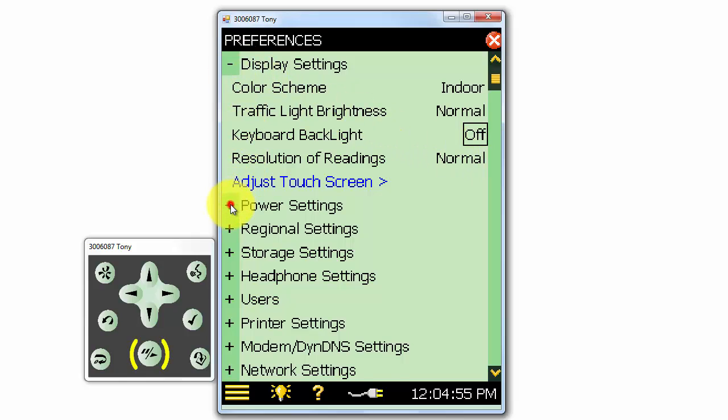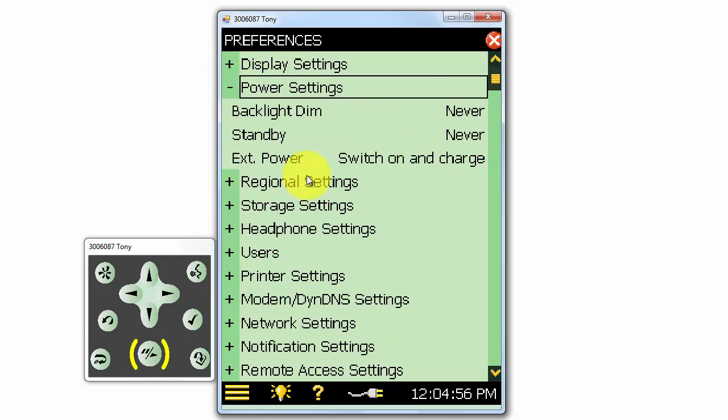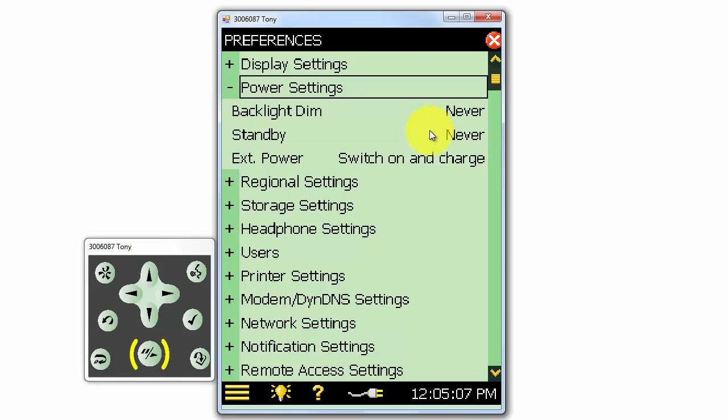The power settings are where we can select how quickly to dim the screen backlight and put the meter into standby mode when it isn't being actively used. These settings can help extend the battery life. The external power selection will allow us to choose whether or not the meter will turn on automatically when external power is applied.